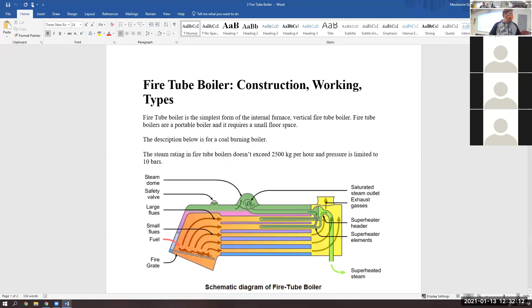This is the simplest form of the internal furnace. We can classify as internal and external furnace. Here we have our fire and combustion, and our gases are inside the shell. The combustion process and flue gases are all inside the shell, and that gas passes over tubes containing water, heating that water. That water, as it becomes steam, transits to a different system, and the flue gases head out into their cycle as well.